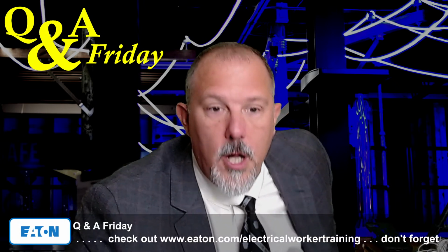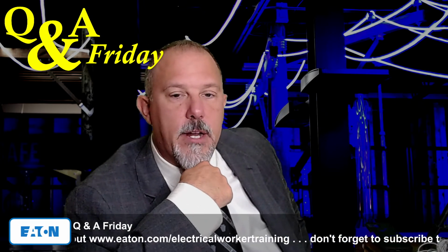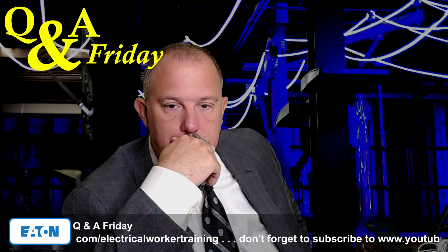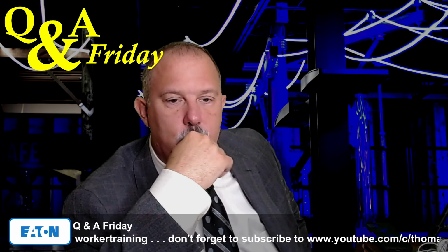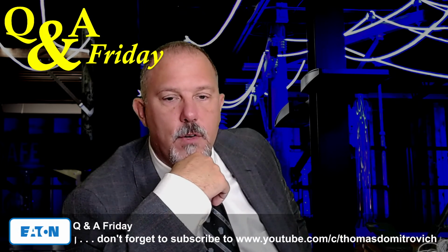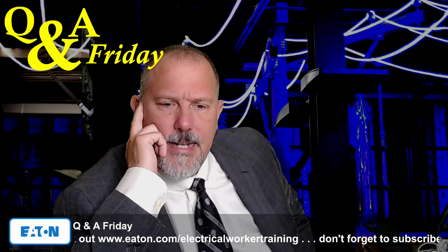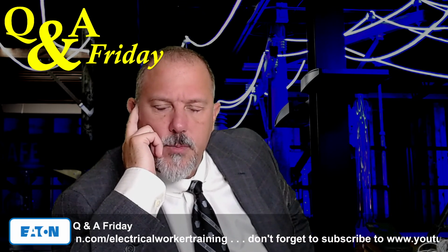You pumped me up. Since the new rule 240.87 may apply when someone is replacing a breaker in a switchboard. Ooh. What happens when someone is installing a downstream breaker over 1200 amps and that breaker was originally configured to be series rated, and now you have to have a fast overcurrent setting for arc energy reduction? It would present a greater hazard to install such a thing, and forcing one to replace the entire switchboard instead of just one breaker is a lot. Let me read that again. Since the new rule 240.87 may apply when someone is replacing a breaker in a switchboard.